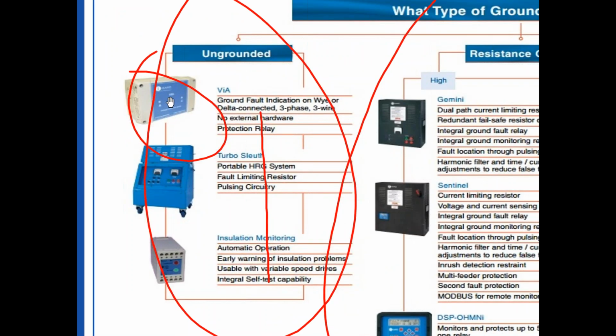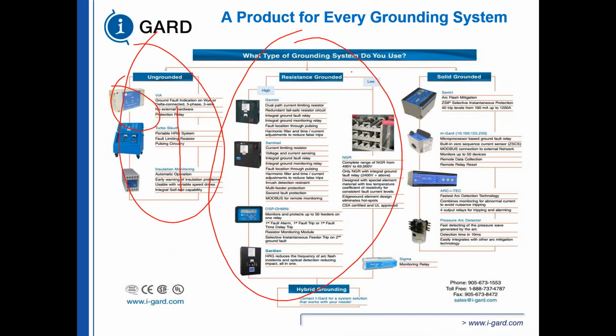We come up with an indication here called the VIA, voltage indication alarm. It's a ground fault detector for ungrounded systems. So rather than having a negative indication that you have a ground fault in an ungrounded system by having one light go out, what we have here is 3 LEDs, and when all 3 are green, that means you have a healthy system. When one phase is faulted, the faulted phase is going to turn red, giving you a positive indication that you have a ground fault, not a negative indication that you have a ground fault.